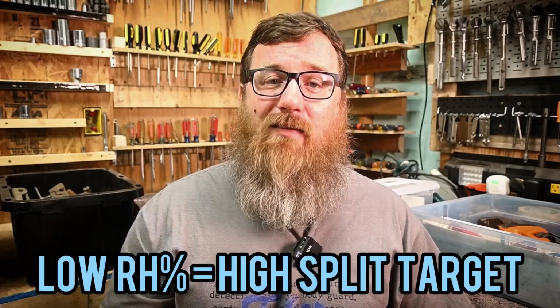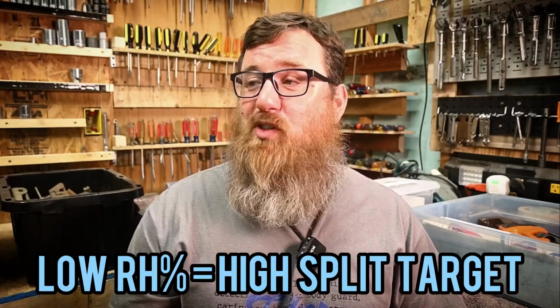By the same token, if you have extremely low humidity, then you're going to get a lot of sensible cooling, which is that actual temperature number that you see on a thermometer. So if it goes in at 80 degrees, it may come out 60 degrees. It may be a 20-degree split because you have an extremely low relative humidity, like 30 or 40%. So basically, all you're looking for is you want your relative humidity, and then you measure your split.